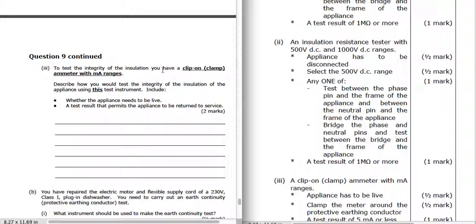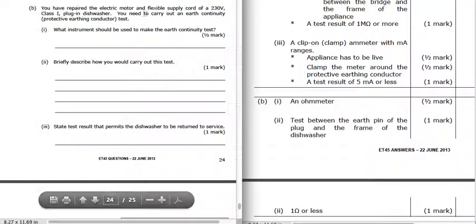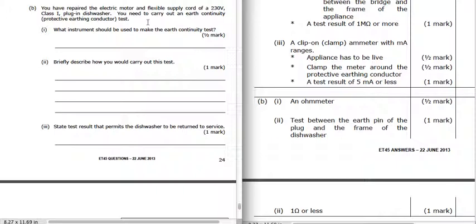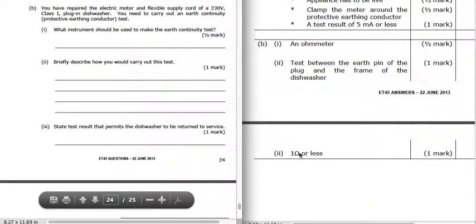To test the integrity of the insulation using a clip-on ammeter with a milliamp range: it needs to be live — plugged in and on — because we're testing for leakage current. Clamp the meter around the protective earthing conductor and look for a current of 5 milliamps or less. Anything over 5 milliamps will fail the test. For an earth continuity test after repairing an electric motor and flexible supply cord, use an ohmmeter. Test between the earth pin of the plug and the frame, and the test result permitting return to service is 1 ohm or less.